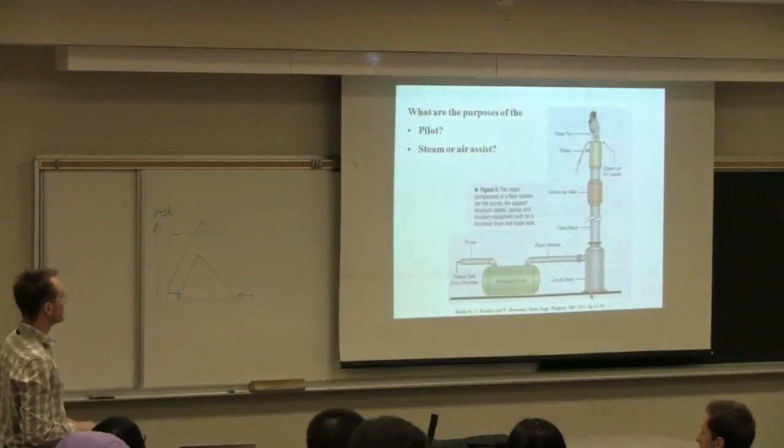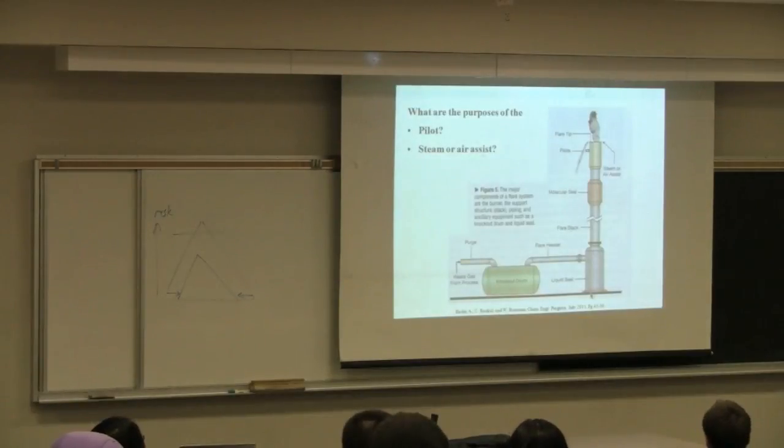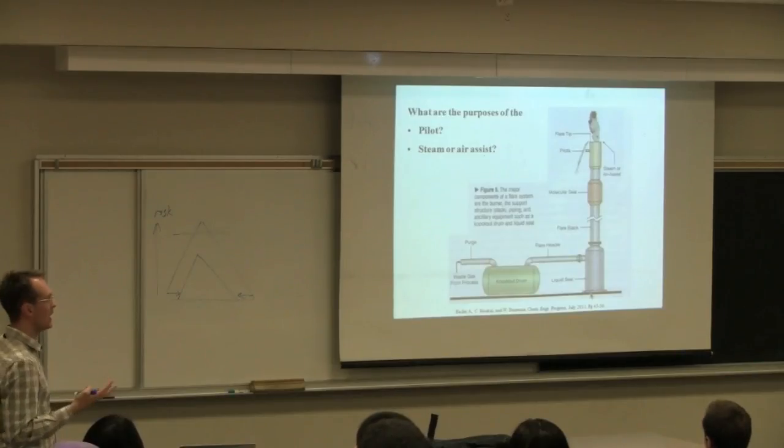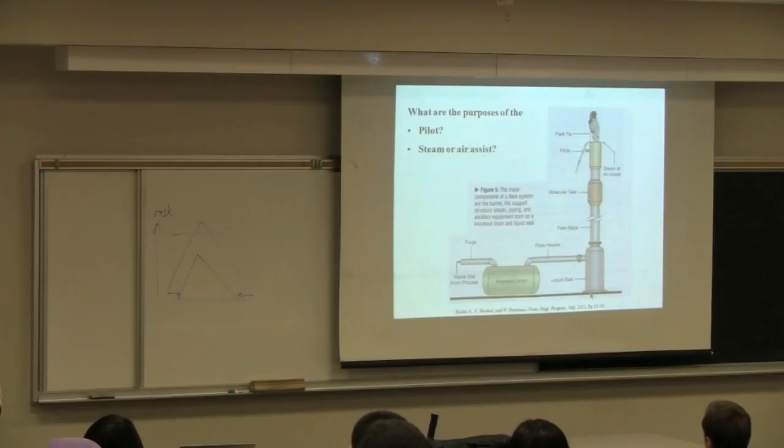These flares also have steam assist and pilots. We don't have too much time to go through this, but I'll just talk about it quickly. Pilots are the small flame that's always present to ensure there is a source of ignition at the top, since the flare may not always be operating. The pilot is heavily monitored, probably more than the flare itself. We can monitor a pilot in multiple ways.